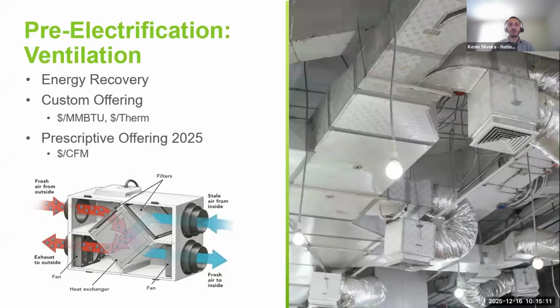So ventilation is a very important part of the formula when we're talking about electrification. Most buildings today bring in outside air, heat it up with either hydronics or a furnace or an RTU, and then you take that nice heated air and exhaust it out through the exhaust systems. Energy recovery ventilation is an important step where we cross those air streams through either an energy recovery wheel or a flat plate heat exchanger to preheat that incoming air. For typical buildings, we're looking at about 40% of your energy use could be just heating ventilation. With an ERV, you can easily reduce that 40%. You can get 20% savings in your building with just an ERV.